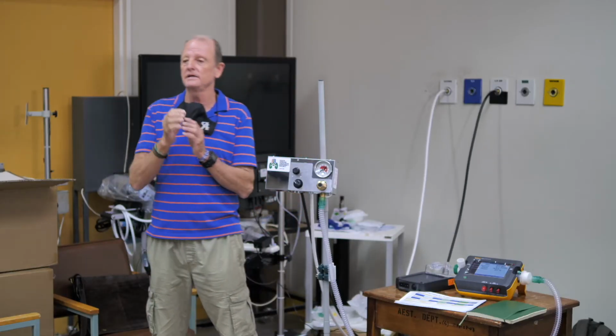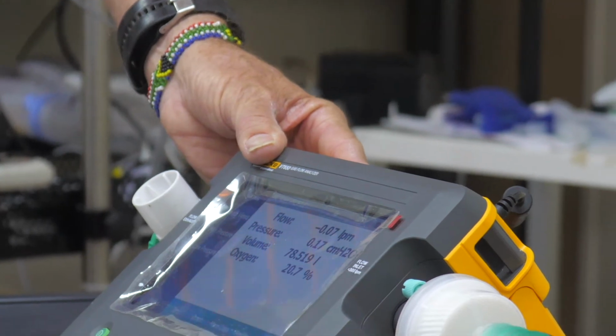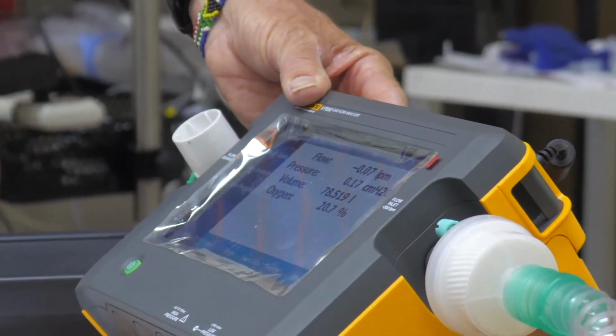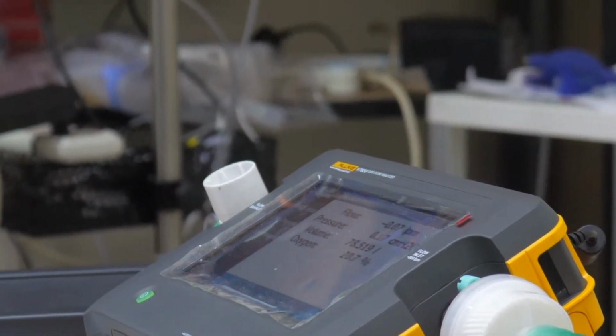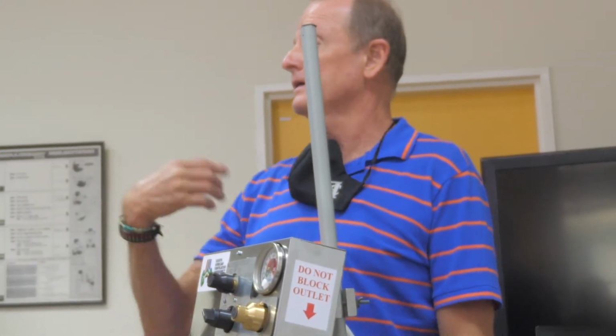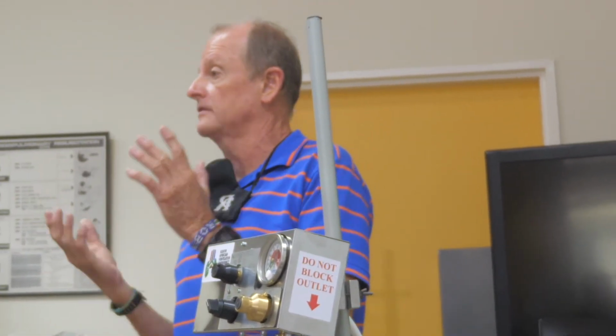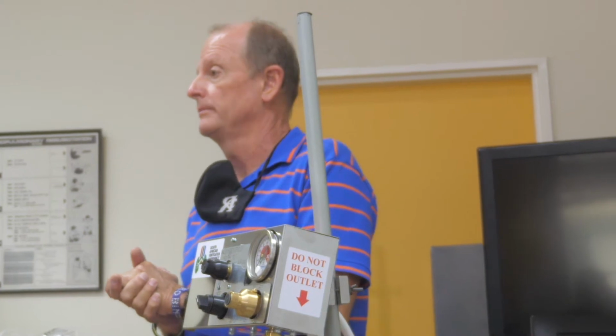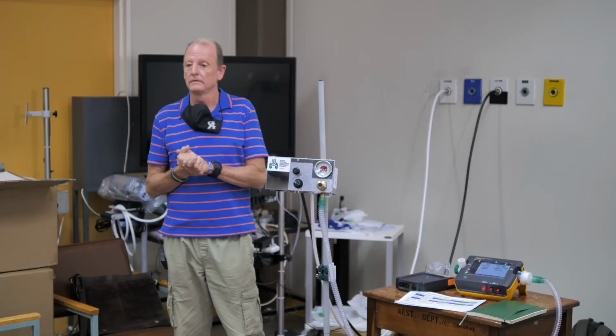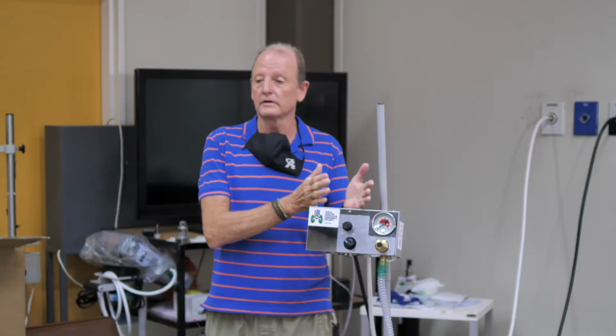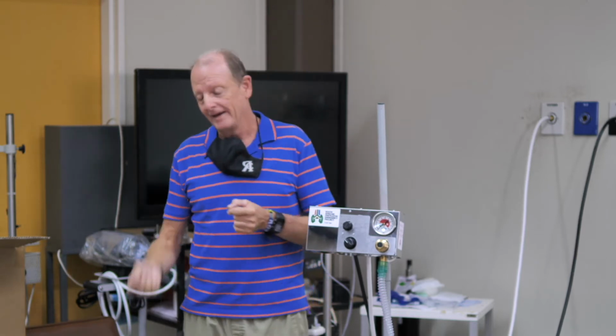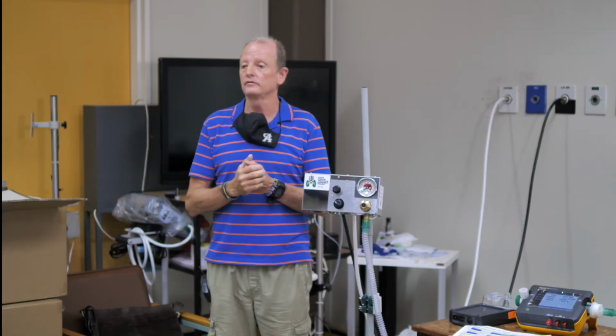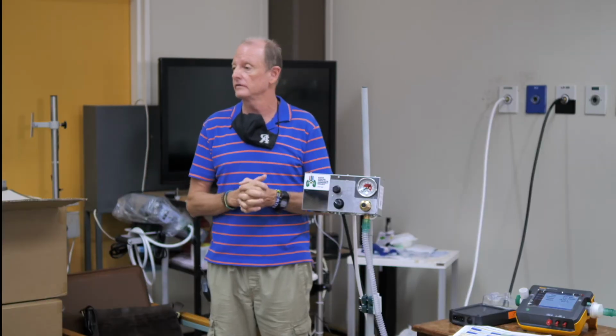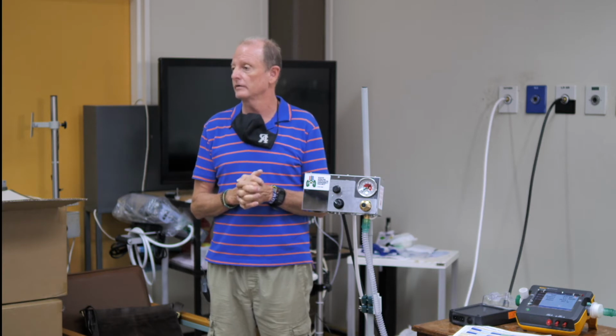Sometimes you get a slight seepage through. These things are very, very sensitive, and it'll pick it up that there's a slight flow. But if you switch it off and it carries on flowing at 4, 5, 6 liters a minute, you've got a problem. Don't try and fix it. A unit like that has to be labeled and sent through, saying there's a problem with that unit, and then it will be returned to us so that we can actually strip it down and have a look at it.